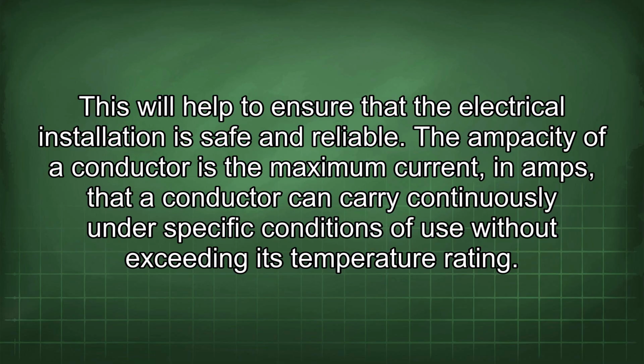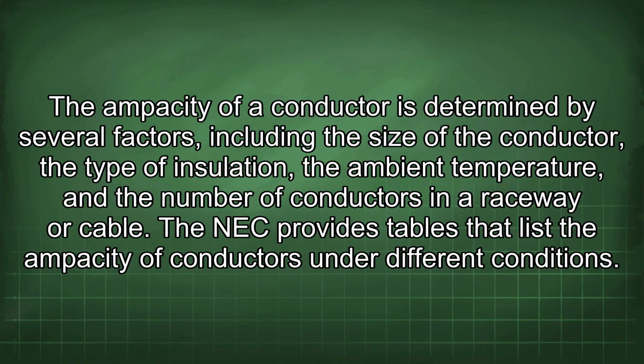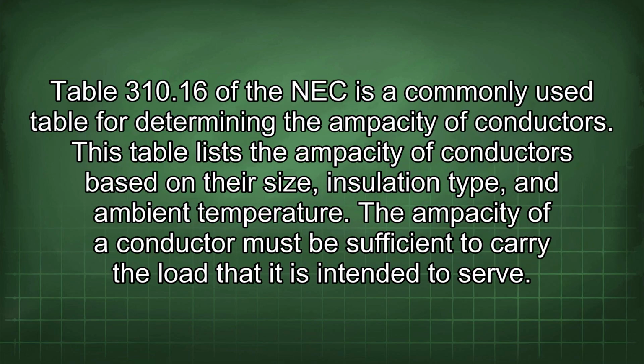The ampacity of a conductor is the maximum current, in amps, that a conductor can carry continuously under specific conditions of use without exceeding its temperature rating. The ampacity of a conductor is determined by several factors, including the size of the conductor, the type of insulation, the ambient temperature, and the number of conductors in a raceway or cable. The NEC provides tables that list the ampacity of conductors under different conditions. Table 310.16 of the NEC is a commonly used table for determining the ampacity of conductors. This table lists the ampacity of conductors based on their size, insulation type, and ambient temperature.